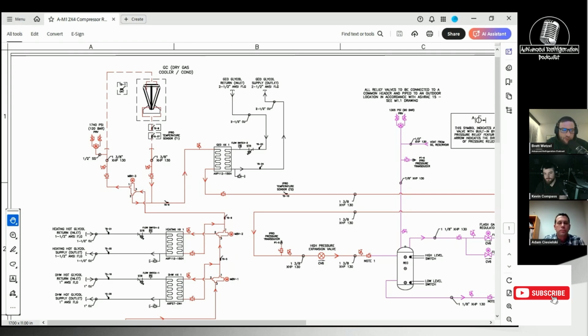So like you said, you want that PID to be fast enough that in the summertime, when it needs to come on and react quickly, it can, but then in the wintertime, you want it slow enough to get more precise control. So maybe the answer is some sort of dual set point where you have an ambient swing where it's going to control one way when it's one temperature versus another. Or, like you stated before, maybe just a lower fast recovery set point.